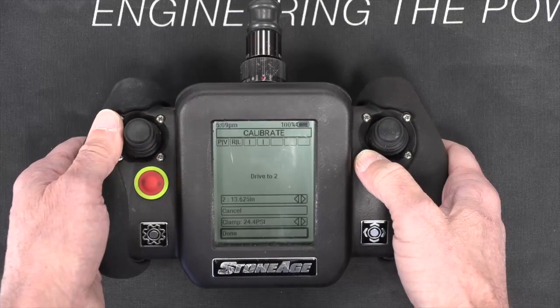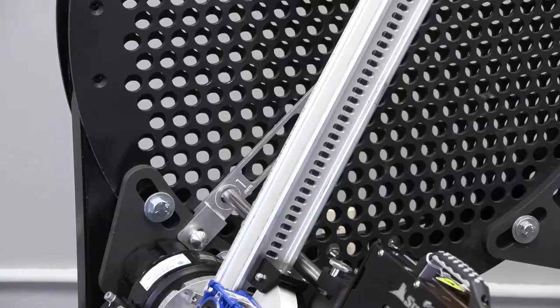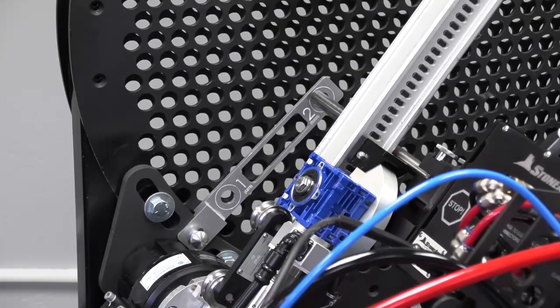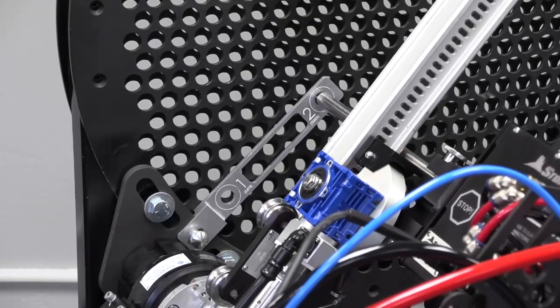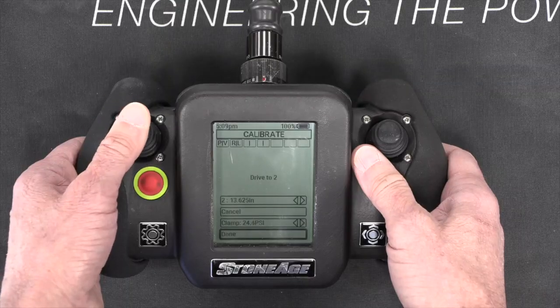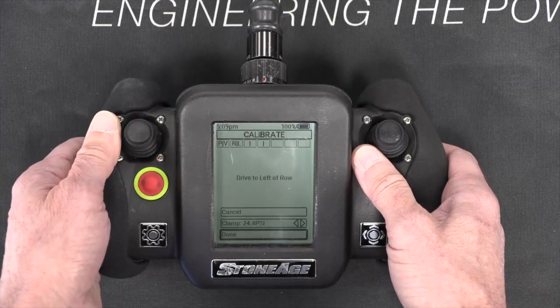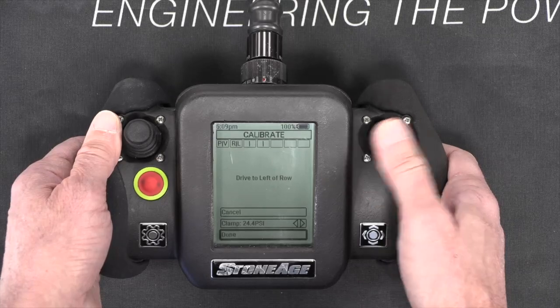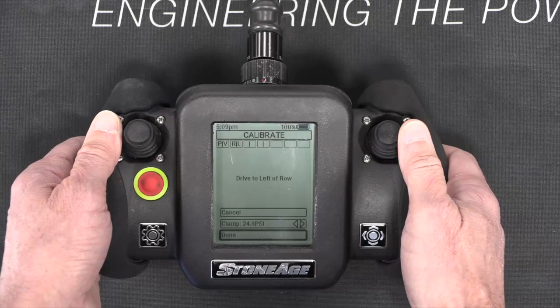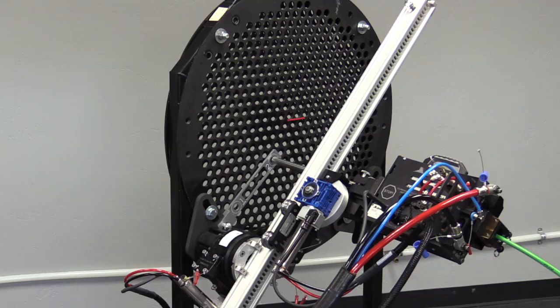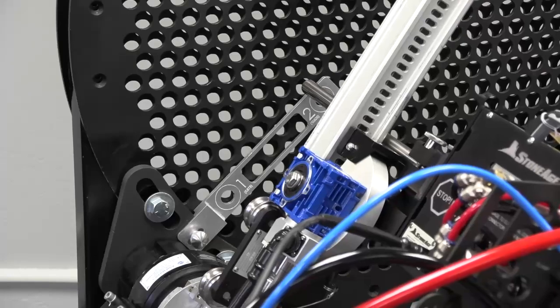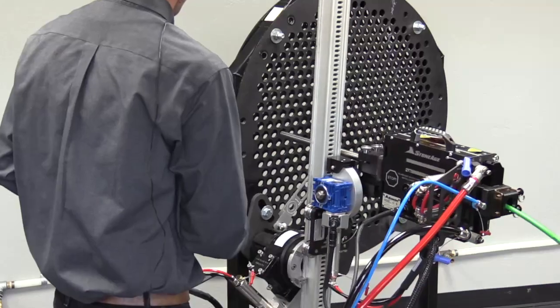Now the display will instruct you to drive to position 2. When you have aligned the guide tube with position 2, click Done. Now you will identify one full tube row to set the horizontal axis of the system. The display will instruct you to drive to the far left tube of one of the rows on the tube sheet. Select a long row for more accurate calibration. It is important that you start and end on the same row.